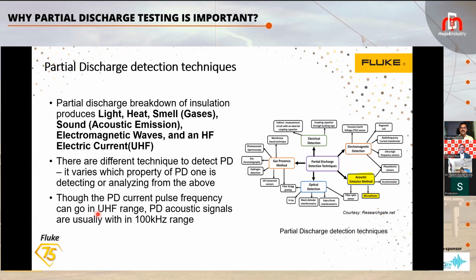Partial discharge creates various frequencies, and the frequency varies for different aspects. Light will have different frequencies, the heat coming out of this partial discharge will be of different frequencies, and electromagnetic waves will be different. The electrical current may be of very high frequencies also. Every technique has unique sensor requirements and unique advantages and disadvantages.